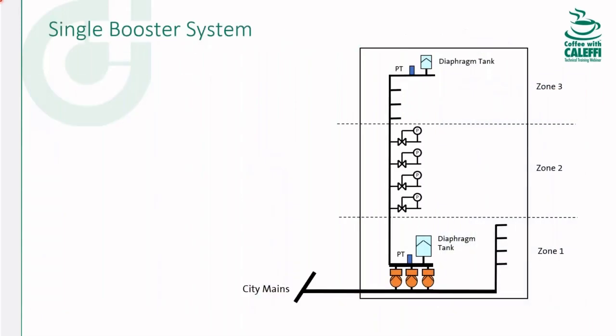Anyway, single booster systems. This is probably the most common of the high-rise layouts. We've got city mains coming in, and that's going to feed zone one, it bypasses the pumps. The city pressure is enough for adequate pressure on zone one. And then you've got the pump system, and that's going to boost the pressure. And so zone two requires PRVs to keep that pressure in check because the pumps have to boost a sufficiently high pressure to have the desired pressure on zone three. So that's why you need the PRVs at zone two.